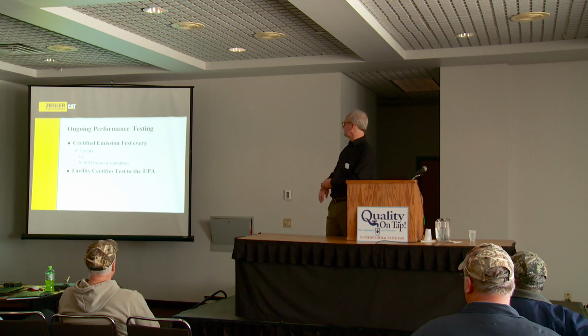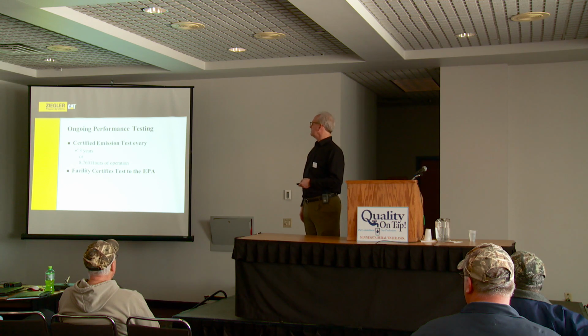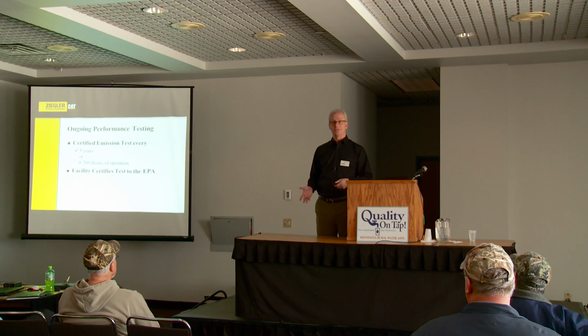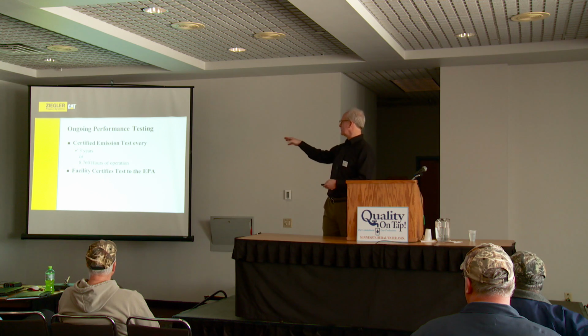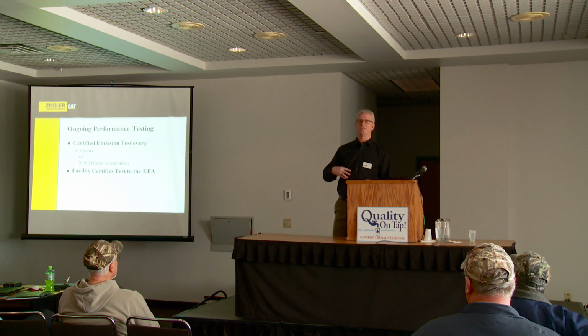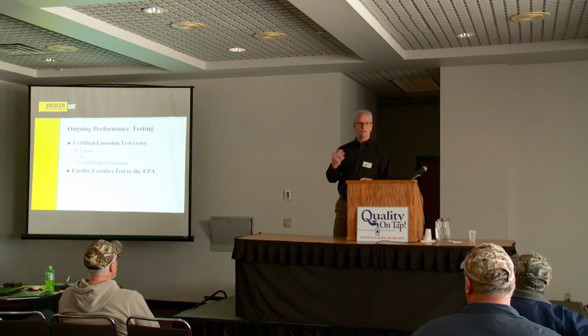And last but not least, 2 minutes left, is the ongoing performance test. So that performance test you had to do in the beginning, you have to do once every 3 years. If you ran your engine a lot, that doesn't really apply to us, 8,760 hours, but for most people, if you ran your engine, in 3 years from now you'd have to do that test again to show that all your emission equipment was working properly.